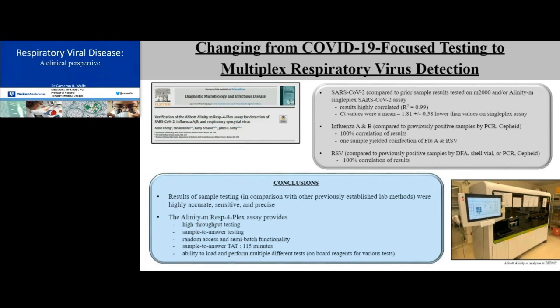In addition, we had 100% correlation of test results for both influenza and RSV for the Resp4plex EUA assay compared to the samples tested previously on other established and approved test methods. This assay, in our view, is a welcomed addition to the targeted respiratory panel options in the post-pandemic world as well.